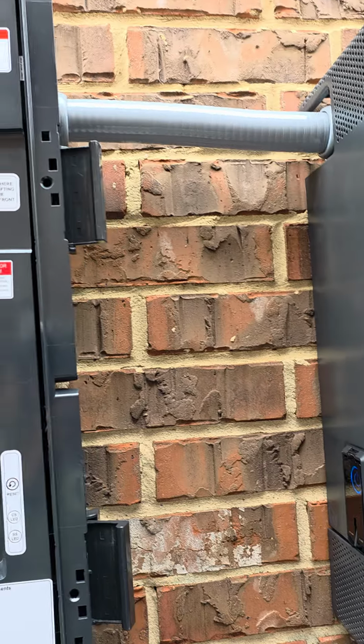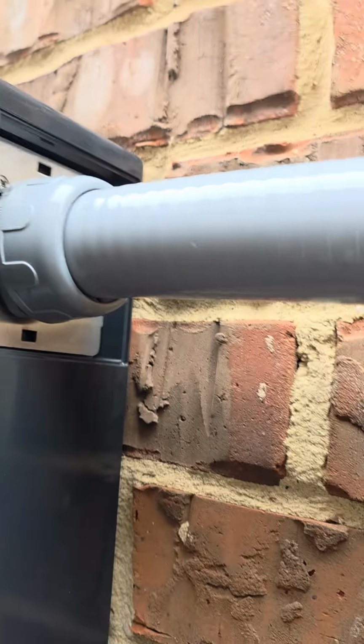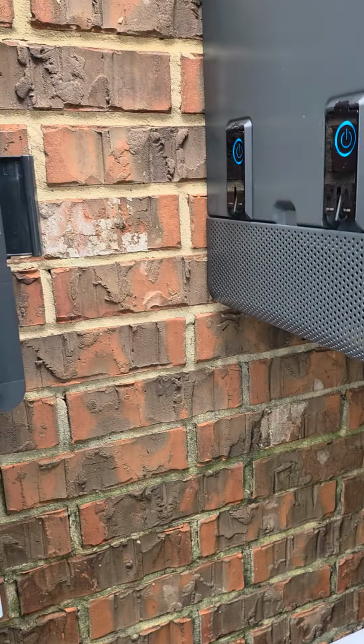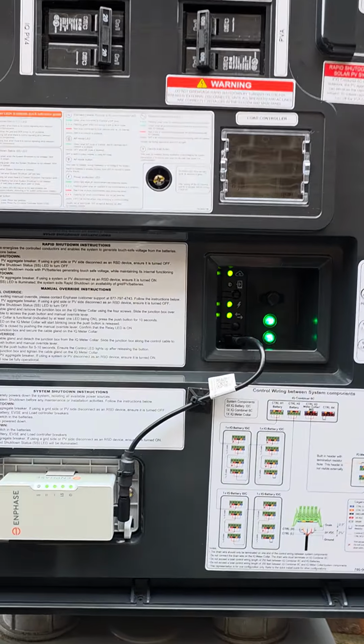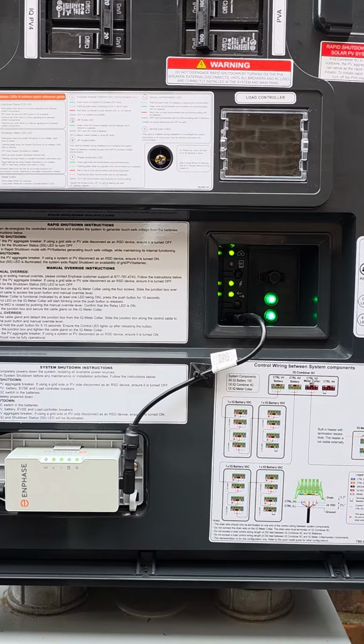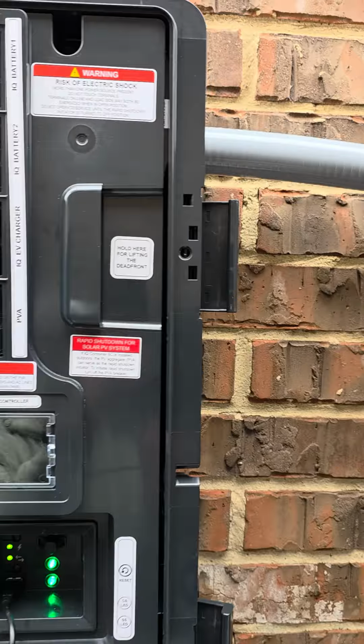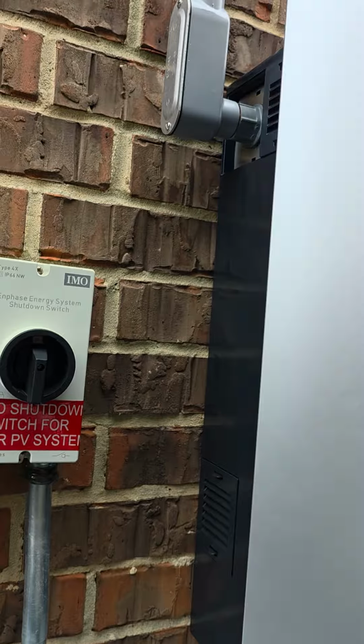And the combiner comes with 3 mounting templates, those metal plates right there. And that was another point of confusion. In the manual, it says that it comes pre-installed with 2 1-inch plates, one on the left side and one on the right side. That is actually not accurate. There are 3 plates total. There's a 1-inch, a 1 1/4 inch, and a 1 and a 3/4 inch template, and that is it. So I utilized the 1 1/4 inch on my battery side, and I used the 1 inch on my solar side, because the previous install was 1 inch. So that worked out pretty well for me.